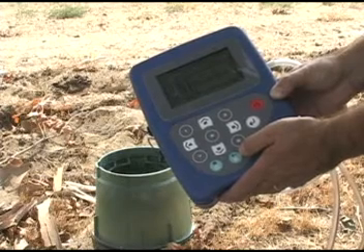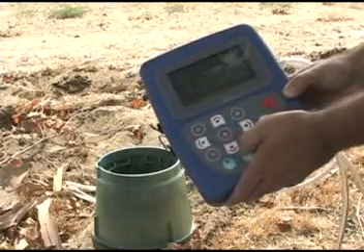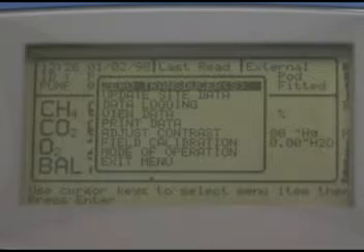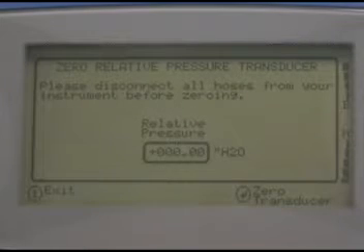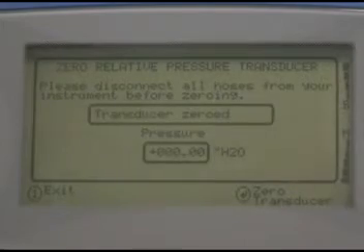The next step is to zero your transducers. Press 1 to bring up the menu. Zero transducers is already selected, so just press enter again. On the zero relative pressure transducer screen, watch the number inside the rectangle. When it is stabilized, press enter.